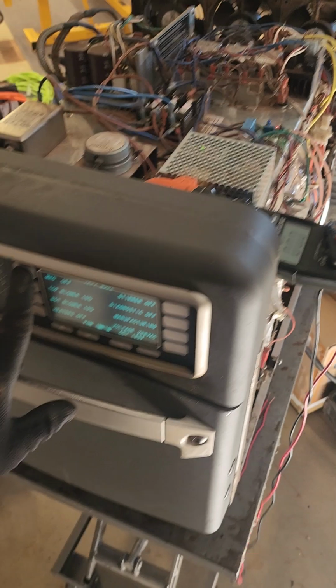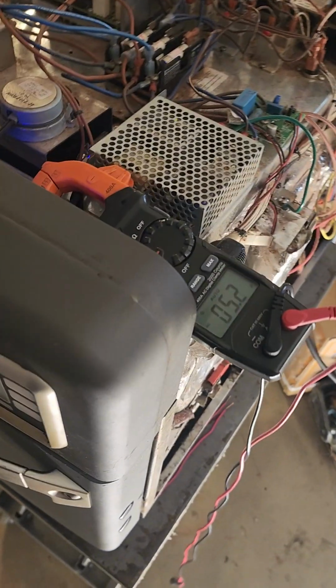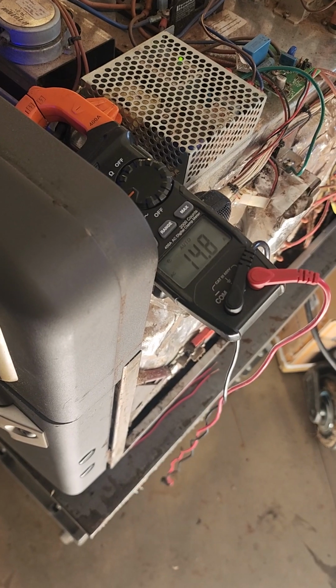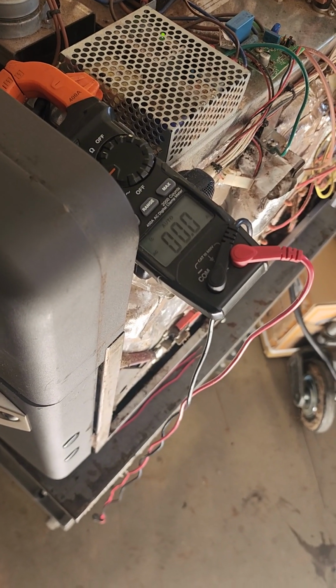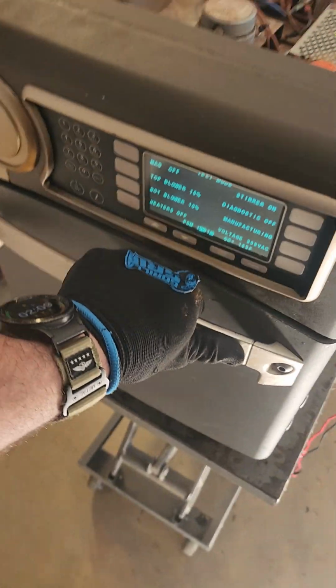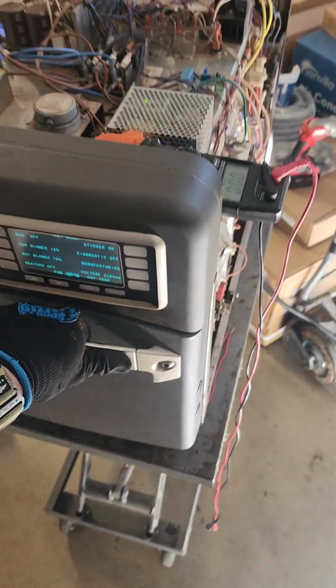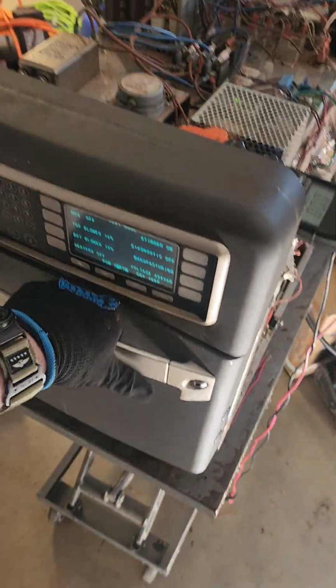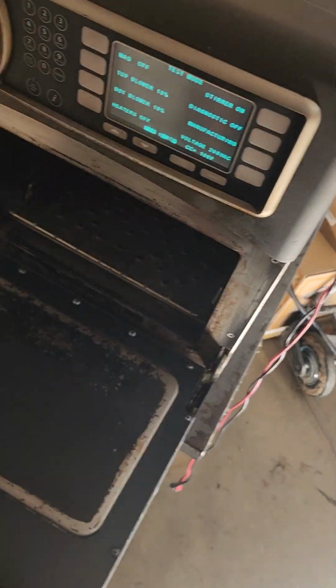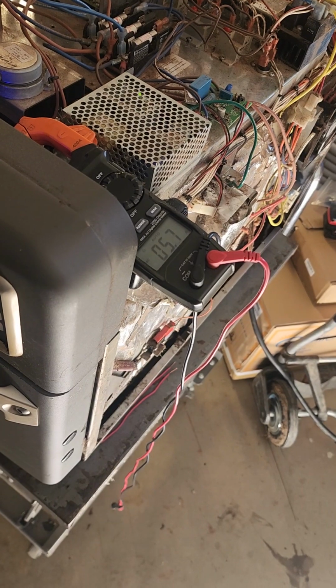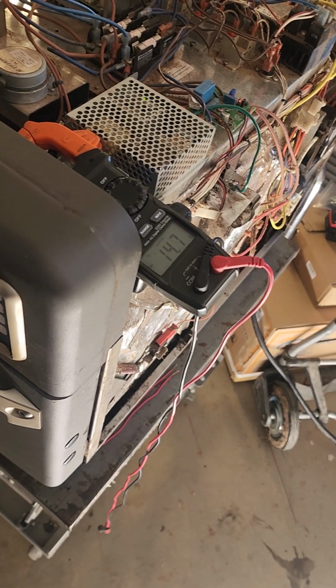The way we check that is we clamp around this brown wire here that goes through that ring on the board. Set to amps on the meter. Press and hold the mag button. That's a good reading. Don't run it for more than a few seconds if you don't have any food in there. If you need to run it for more than that to test, you can take a wet rag and put that in there. It's not good to run it without a load for more than a few seconds. And open the door between tests. Run it a couple times. That's good.